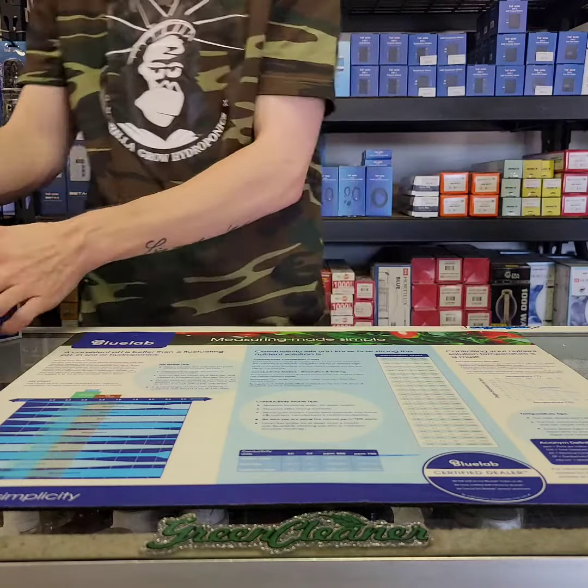Now these do have an expiration. The 7 and the 4 both go bad after a couple of months, so you definitely want to make sure that you keep those fresh. Now as soon as we dunk this into the water here, we'll see that there's not much change, but as soon as I start to swirl it, that number starts to go up. This is mostly because the storage solution is coming off. Once you do get that off, you'll notice the numbers start to go back down.